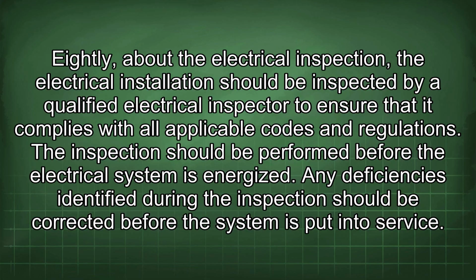Eighthly, about the electrical inspection. The electrical installation should be inspected by a qualified electrical inspector to ensure that it complies with all applicable codes and regulations. The inspection should be performed before the electrical system is energized. Any deficiencies identified during the inspection should be corrected before the system is put into service.